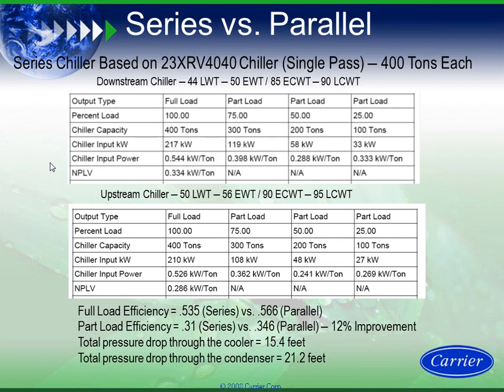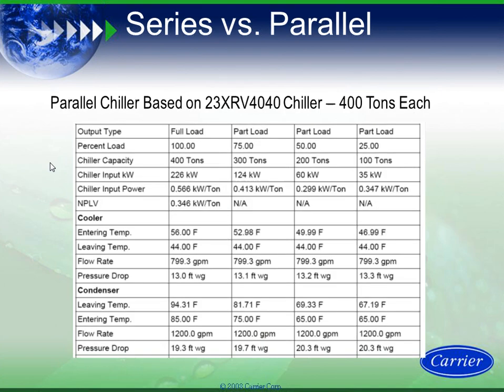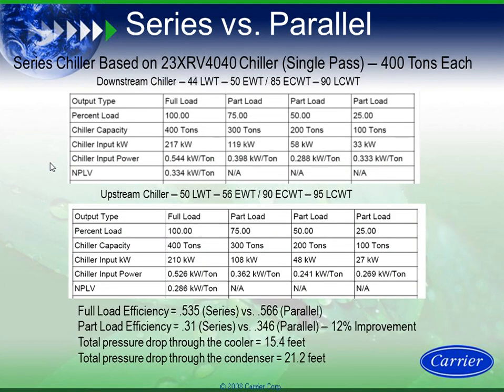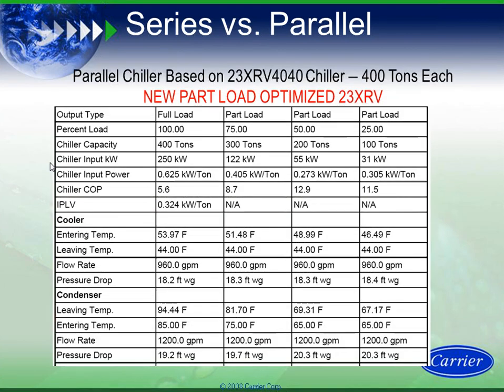My total pressure drop on the condenser in series is 21.2 versus the previous, which was 19.3 and 13. So I take a tiny penalty on the pressure drop, but I gain tremendous amounts of efficiency on the chiller. Now let's do the same exact thing.